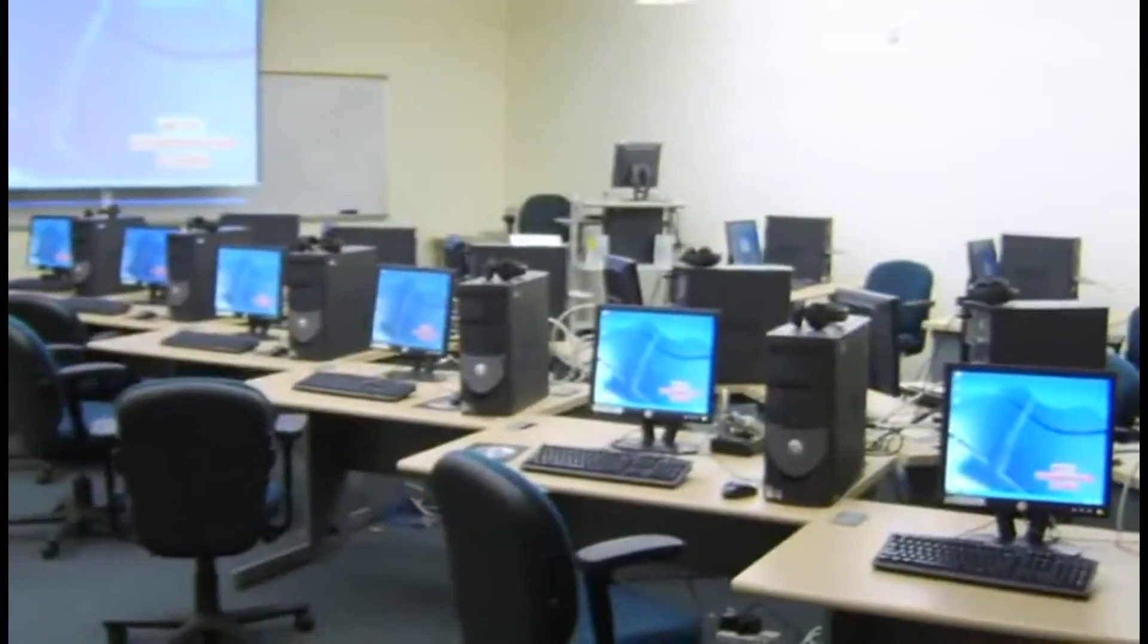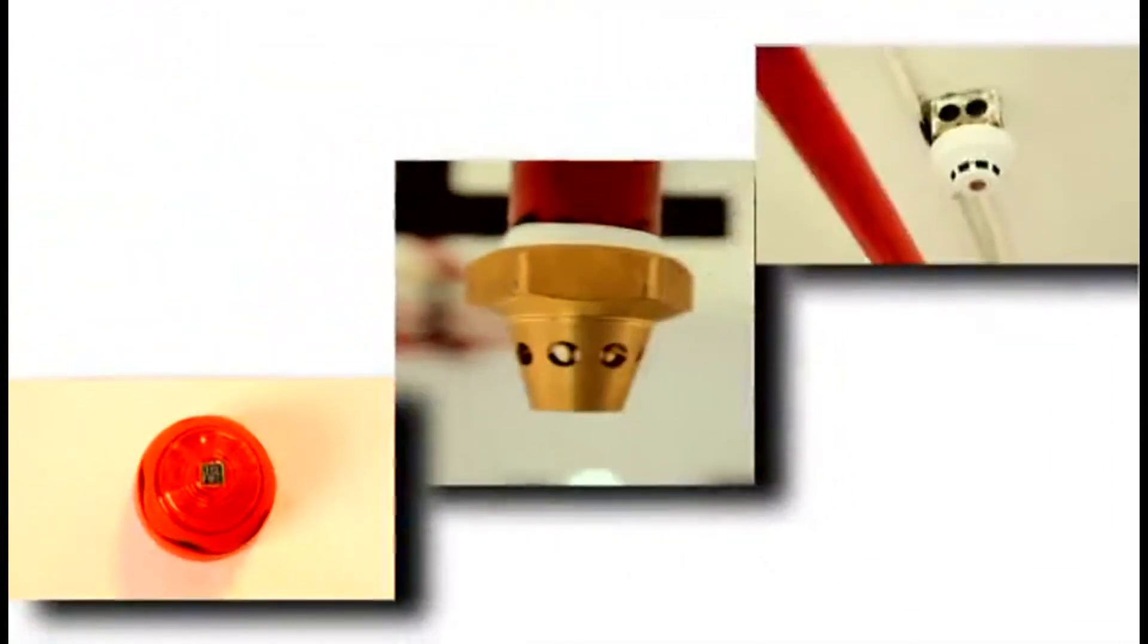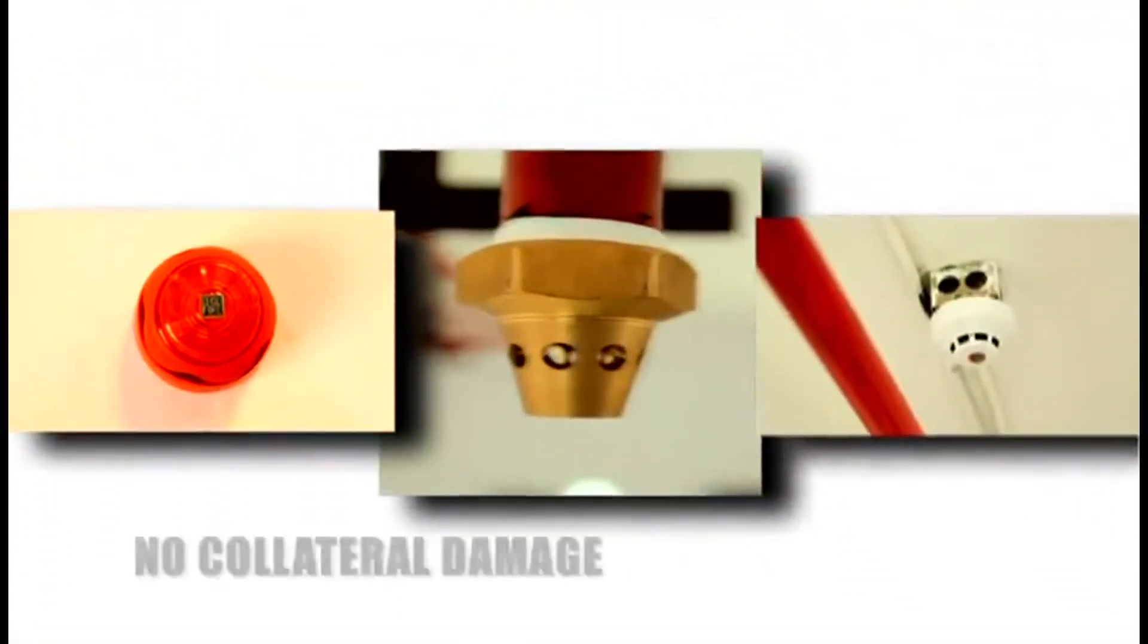The system reaches extinguishing levels in 10 seconds or less, stopping ordinary combustible, electrical and flammable liquid fires before they cause significant damage. And there's no clean-up required, as the extinguishing agent can be removed by simple ventilation. It's also designed to prevent re-ignition and not leave behind any collateral damage.